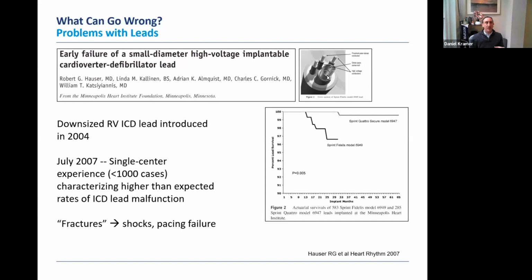When that happens, a few things can occur that interfere with the way the device paces patients. It can also cause noise on the signals the defibrillator sees. That's unfortunate, because the defibrillator will interpret that signal as a dangerous arrhythmia and deliver a shock that the patient didn't need. In some cases, that inappropriate shock, as we sometimes call it, can actually be fatal.